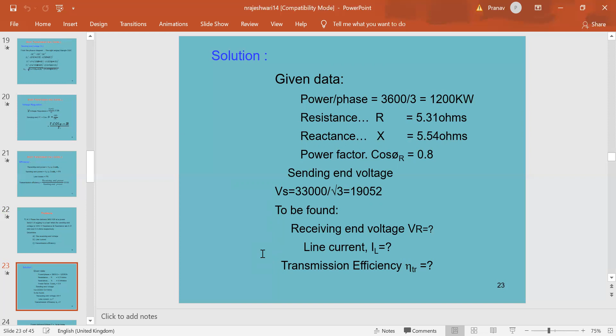For this, first we have to find the receiving end voltage VR. The power delivered per phase is P is equal to VR I cos phi r, so I is equal to P by VR cos phi r. We have the power, the sending end voltage and the angle, and from this we will create one relation between VR and I. So I is equal to 1200 kilowatts, that is 1200 times 1000, divided by VR into 0.8, the power factor. By simplifying this, I is equal to 15 into 10 to the power of 5 divided by VR.